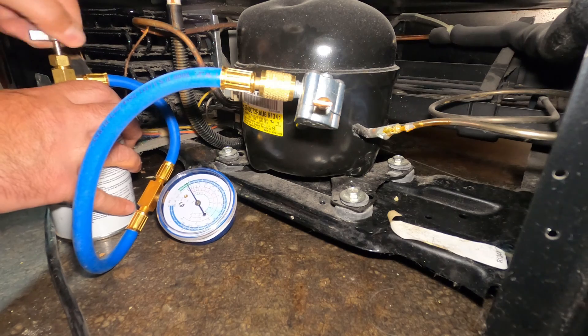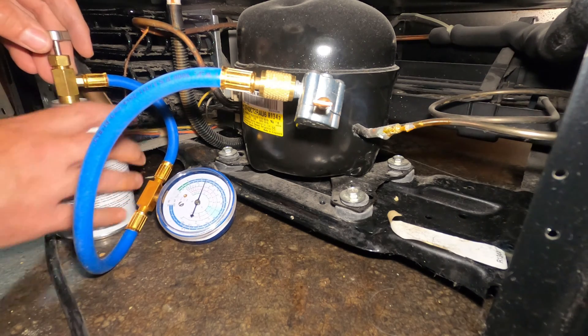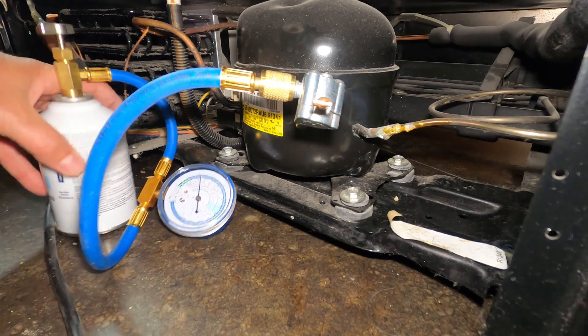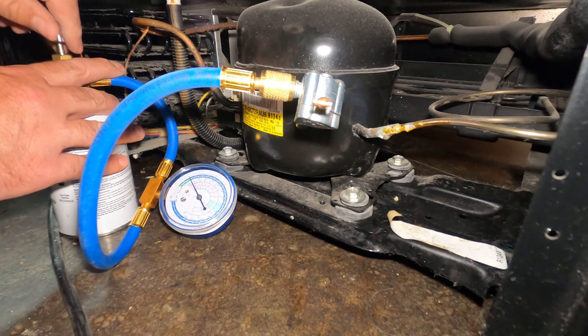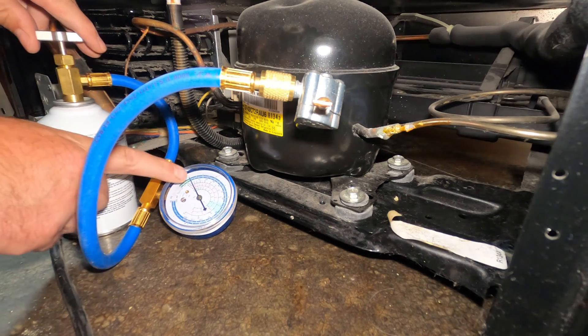Open the gas line — you're starting to see it. I want to fill at a controlled rate to keep it just where I need it. I'm going to fill it at about the 12 PSI rate and shake it a little bit to make sure it fills. I don't want to charge too much. You see how it still goes down to zero — we were negative before, now we're at zero. I'm going to bring it up to the 20-25 range.